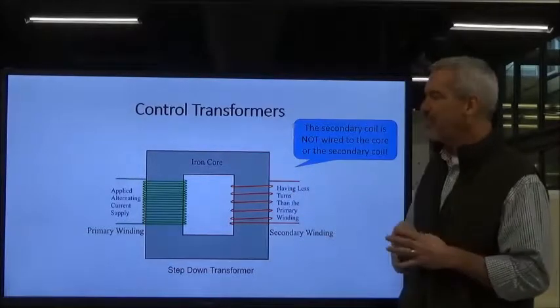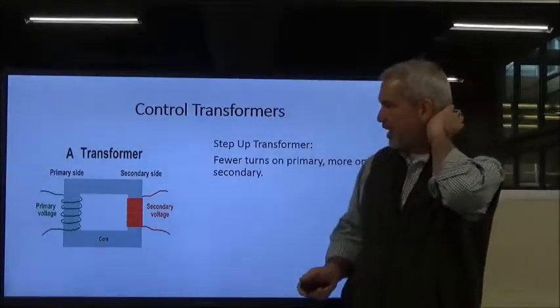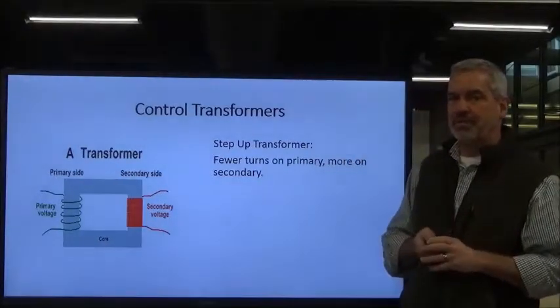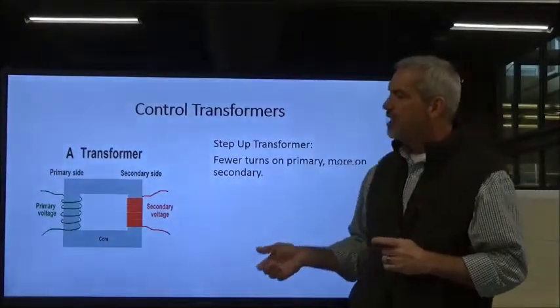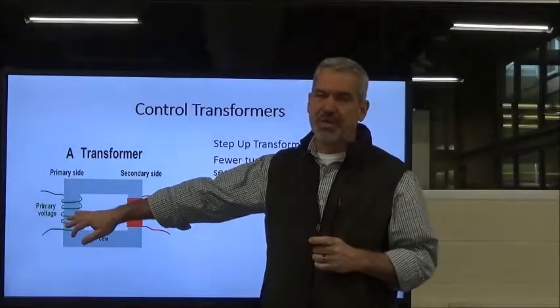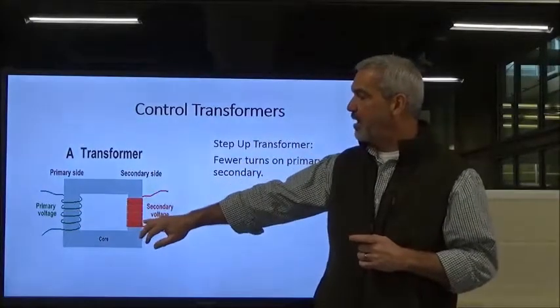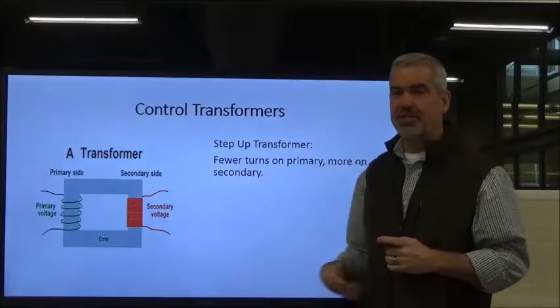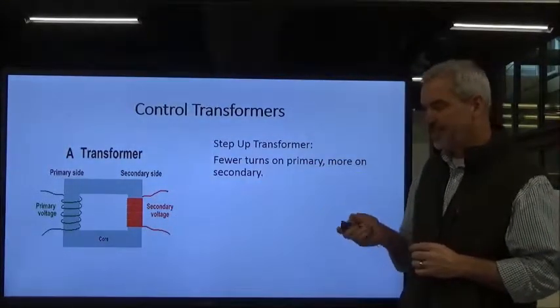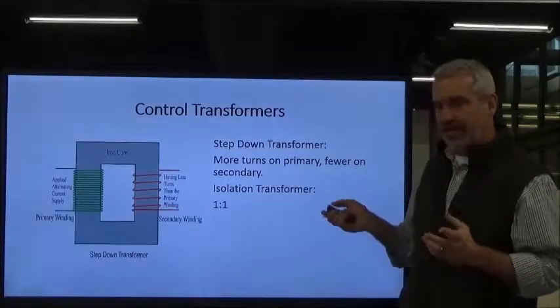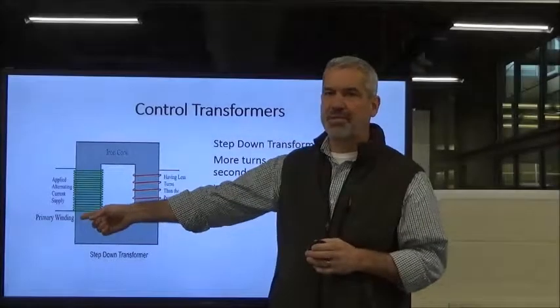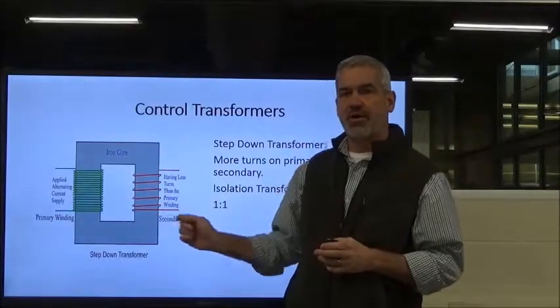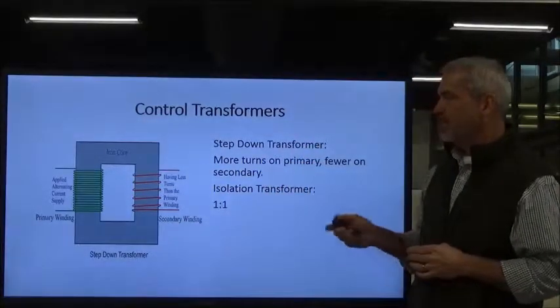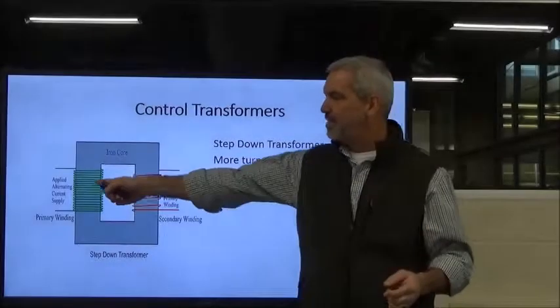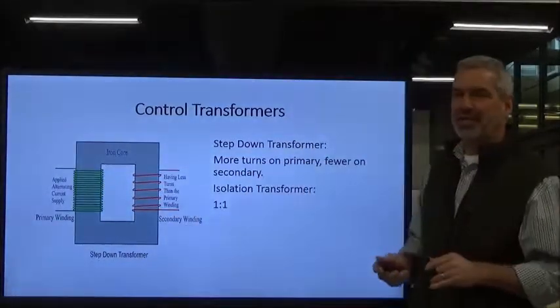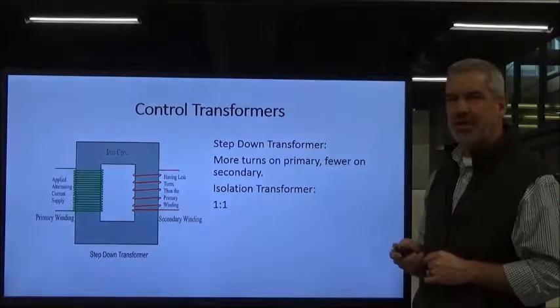So that's critical for you to remember, all right? On a step-up transformer, that's the opposite of what we were looking at previously. With a step-up, you're going to have fewer turns on your primary side and more turns on your secondary side. Just the opposite with the step down. With the step down, we've got more turns on the primary side and fewer turns on the secondary side. And with an isolation transformer, we've got 1-to-1, the same number of turns on both sides. We're not going to really get into isolation transformers much in this class.